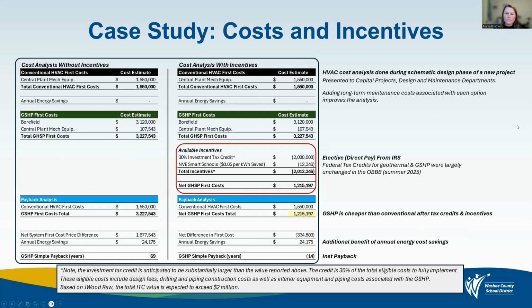So on the new project that I mentioned we just got approved, we did have to do a financial analysis comparing a traditional heat pump or traditional construction mechanical system with boilers and chillers against this ground source heat pump system. As you can see, without the incentives, doing the bore field and installing the geothermal heat pump system, the plant itself was about $2 million more than what a traditional system would be.